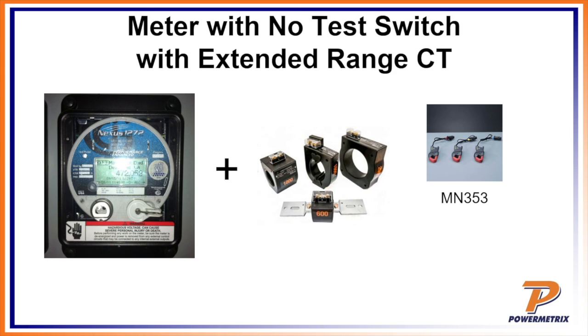That's a great point, Chris. So the nice thing about the 353, you get versatility from 0 to 200 amps, but usually you lose a little bit of accuracy. The smaller the range, the more accurate you can keep that probe. That's why the MN114s are a fantastic probe, 0 to 10 amps. But if you've got a little bit more current, you can use the 353, but you may sacrifice a little bit of accuracy to measure that lower end of the curve on the probe.